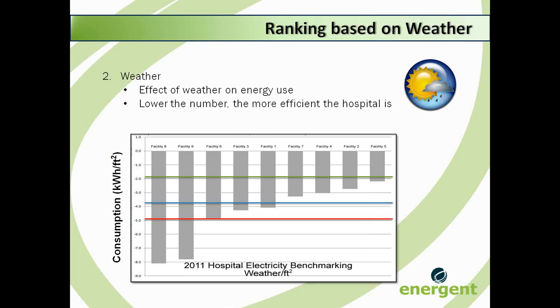This graph is focused on how much energy is needed to maintain the temperature and humidity set points in the hospital. We have ranked the facilities from the worst performers on the left to the best performers on the right. This range of consumption is approximately 8 kilowatt hours per square foot for the worst performers, and just over 2 kilowatt hours per square foot for the best performers.